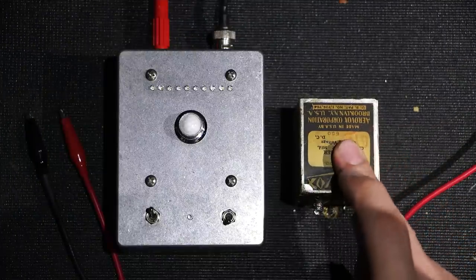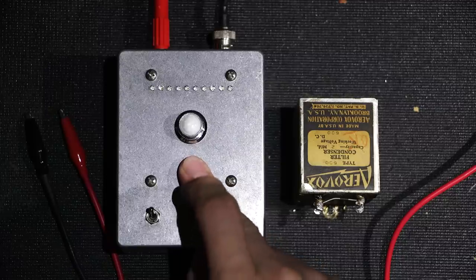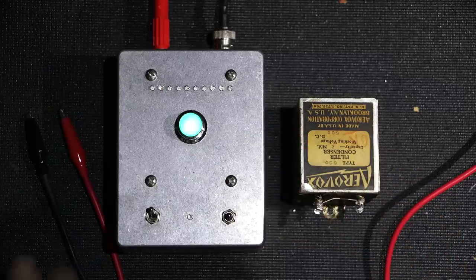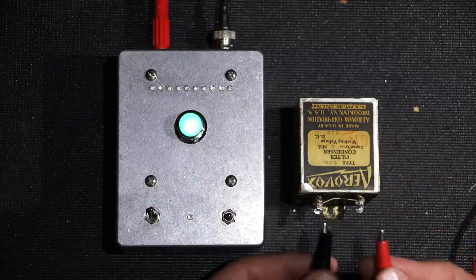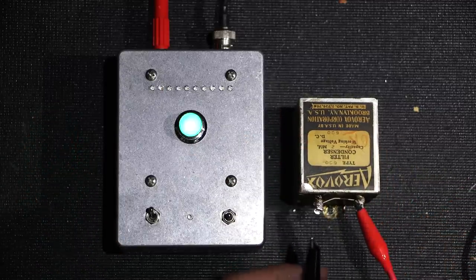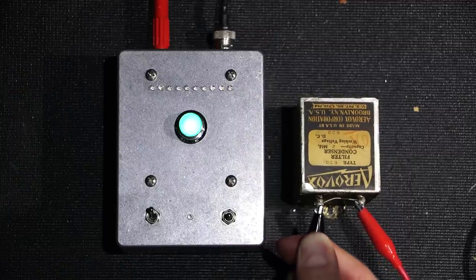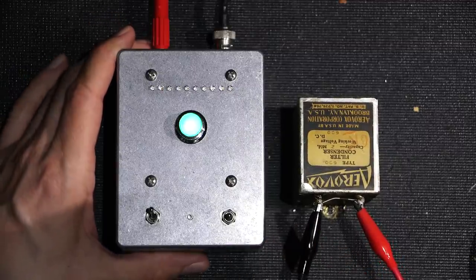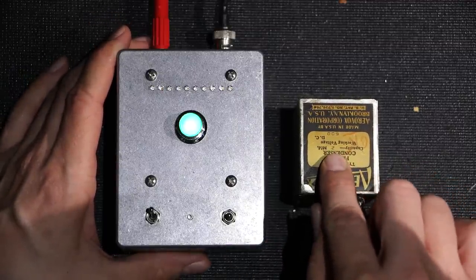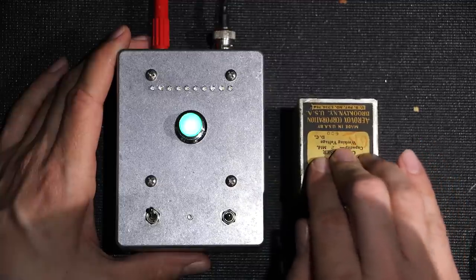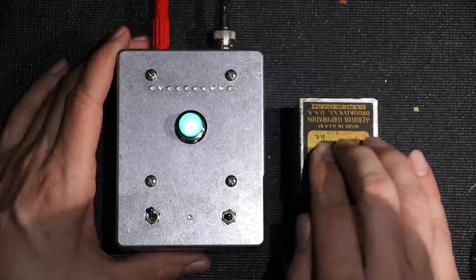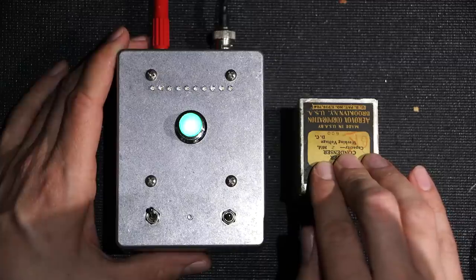Let's test this capacitor for leakage using the new leakage tester. So I'll click this onto discharge here and I'll explain exactly how I'm going to test this. I'll attach this here and here. It is in the discharge position, so it's not testing it right now. Now this is 2 microfarad and it's going to take a fair amount of time to charge this capacitor, so what I'm going to want to do is fast charge this in the electrolytic position.